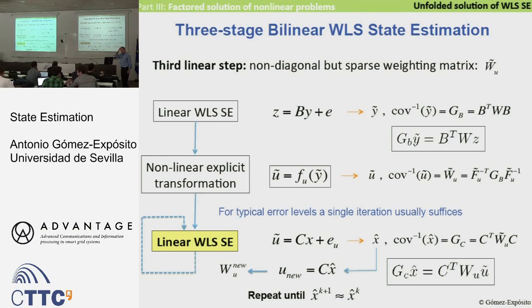Can you try to normalize the data in the beginning and see which values seem to be really far away? Or is it not possible? I don't think so, particularly when there is low redundancy. It's risky. This is heuristic, and here you must resort to statistics rather than heuristics. There is a prefiltering stage when there is a lot of redundancy. In transmission substations, they check whether the power flows at the two terminals are very different, because the losses are small, 2%. So they can detect or prefilter bad data, or a voltage that cannot be negative, for instance. So there are some very basic preliminary checks. But apart from that, you shouldn't remove any measurement unless it's clear to you that it's bad.